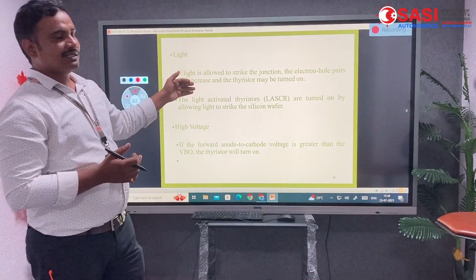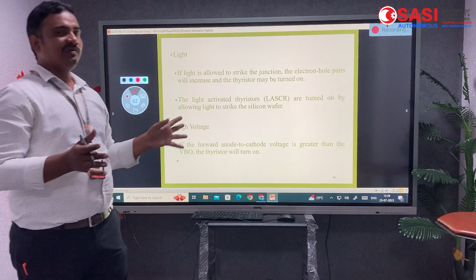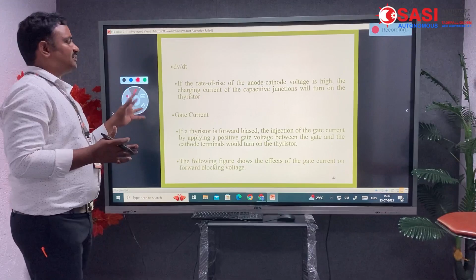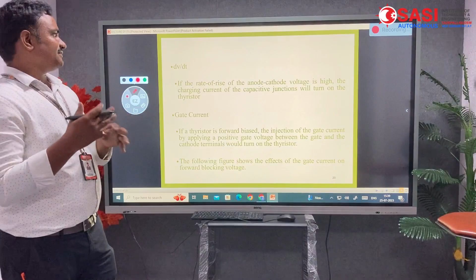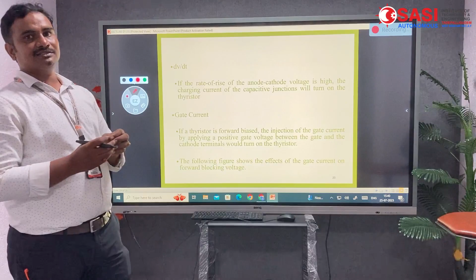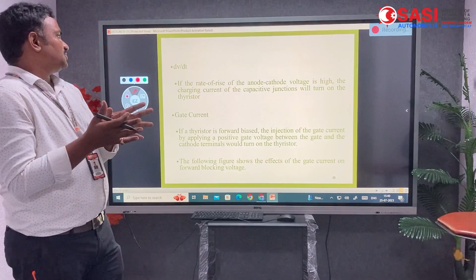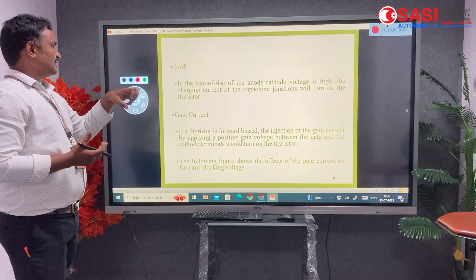Another method is to apply high voltage, that is, applying an anode to cathode forward voltage more than the breakover voltage. If the forward anode to cathode voltage is greater than VBO, then the thyristor will get turned on. This is one of the regular methods to turn on the SCR. The next one is to change dV by dt, which is the change in voltage with respect to time. If the rate of rise of the anode to cathode voltage is high, because of some reason there is a change in voltage with respect to time, so the charging current of the capacitive junction will turn on the thyristor. That means there is a capacitance formation at the junctions J1, J2, J3, that is CJ1, CJ2, CJ3, which will influence the junctions to give a current flow between the anode and cathode.